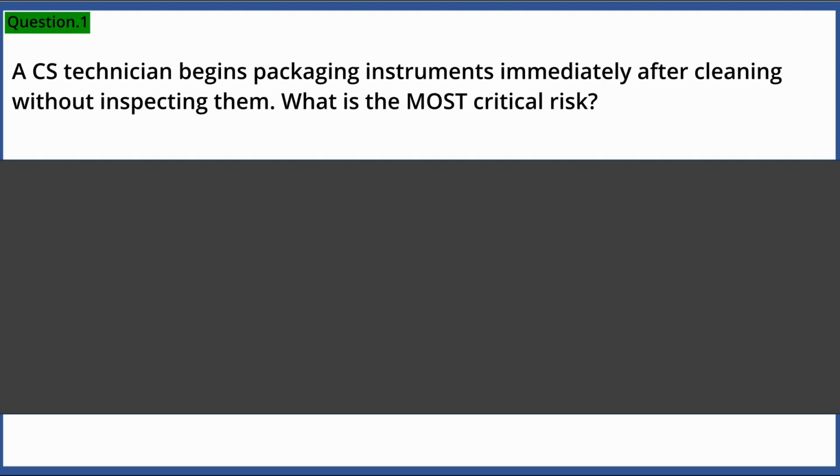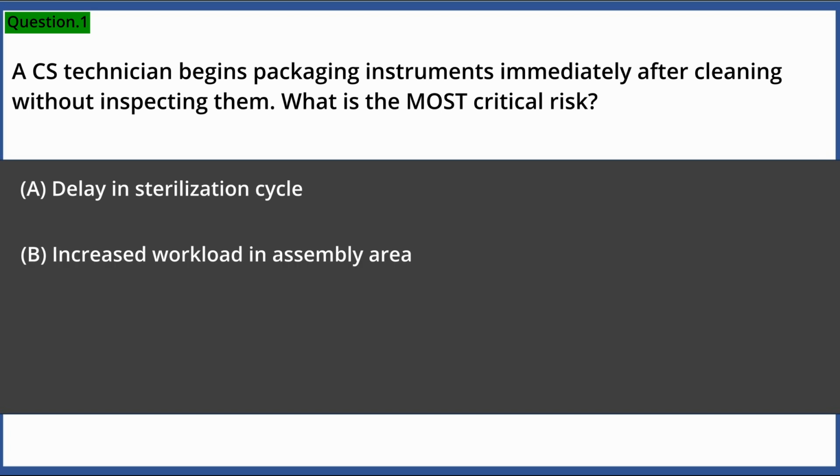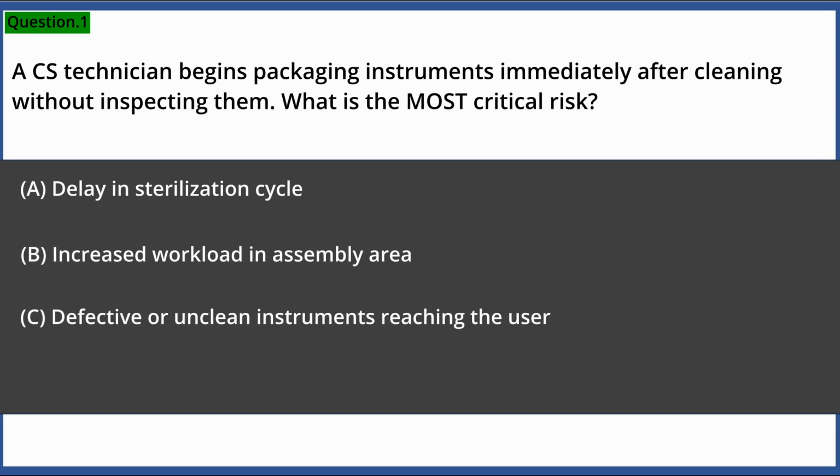A CS technician begins packaging instruments immediately after cleaning without inspecting them. What is the most critical risk? A. Delay in sterilization cycle. B. Increased workload in assembly area. C. Defective or unclean instruments reaching the user. D. Incorrect labeling of packages.